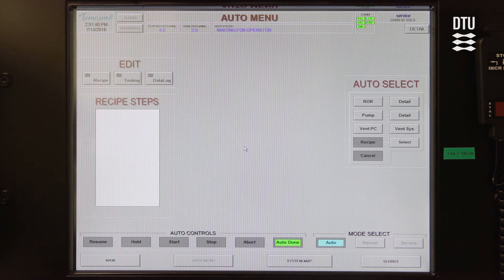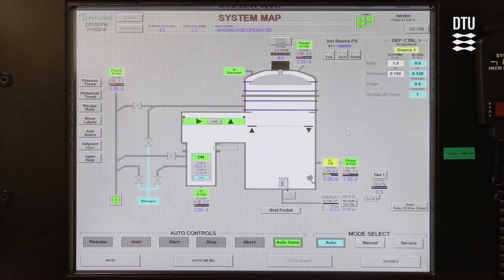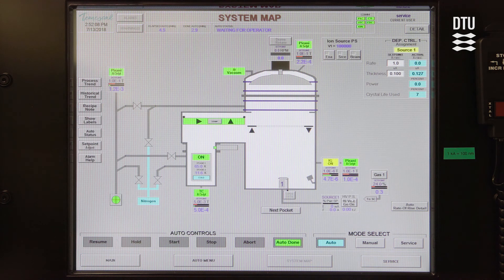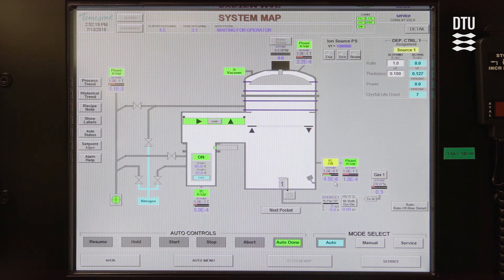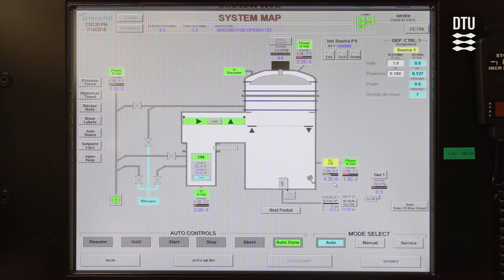Now you're ready to start a recipe in principle, however the pumping takes about 20 minutes. You can go to the system map and see what the pressure is at the moment. Before the pressure is low enough for deposition — which is 1 times 10 to the minus 6 torr — you will see that the ion gauge symbol is yellow. There's still some time before we reach a low enough pressure. If you want to go check your email, wait to start the recipe, because if you start a recipe the deposition will begin spontaneously as soon as it reaches low enough pressure. Come back when the pressure is low enough and then start your recipe.